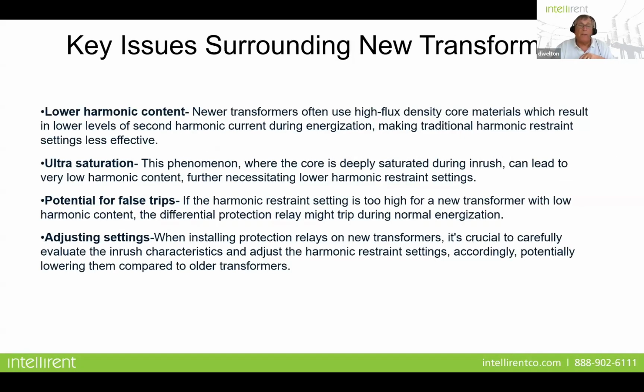Now, there's a couple of things that you have to be careful of, especially with new transformers, because traditionally, whether you had a BDD relay or an HU relay or the old electromechanicals, they were kind of set statically at 20% or 25%, because that's normally what you'd see in transformers. Well, what we find is that new transformers use high flux density core materials, and that results in lower levels of second harmonic current during the energization. So that makes your harmonic restraint setting less effective. You have ultrasaturation, which is a phenomenon where the core is deeply saturated during the inrush, and that can lead to also very low harmonic content.